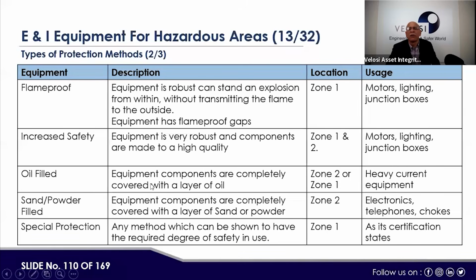Then oil filled. Normally these are transformers, junction boxes, and switchgear installed inside the substations. The equipment components are completely covered with a layer of oil. These are heavy current equipment like transformers and switchgear. Similarly, sand or powder filled equipment has components completely covered with a layer of sand or powder. These are electronics, telephones, or chokes. Then any method which can be shown to have the required degree of safety in use for zone 1 is special protection, as its certification states.